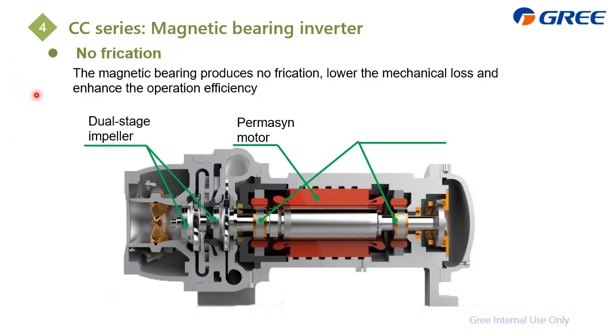And this is the CC compressor. What is the difference between this and the previous one is the impeller. This part is the same. The motor is almost similar. It can change the RPM. What's different is this bearing. It is a magnetic bearing, which means the shaft does not touch the bearing. This can definitely lower the friction. And also we don't need oil for lubrication as they don't touch together, right?